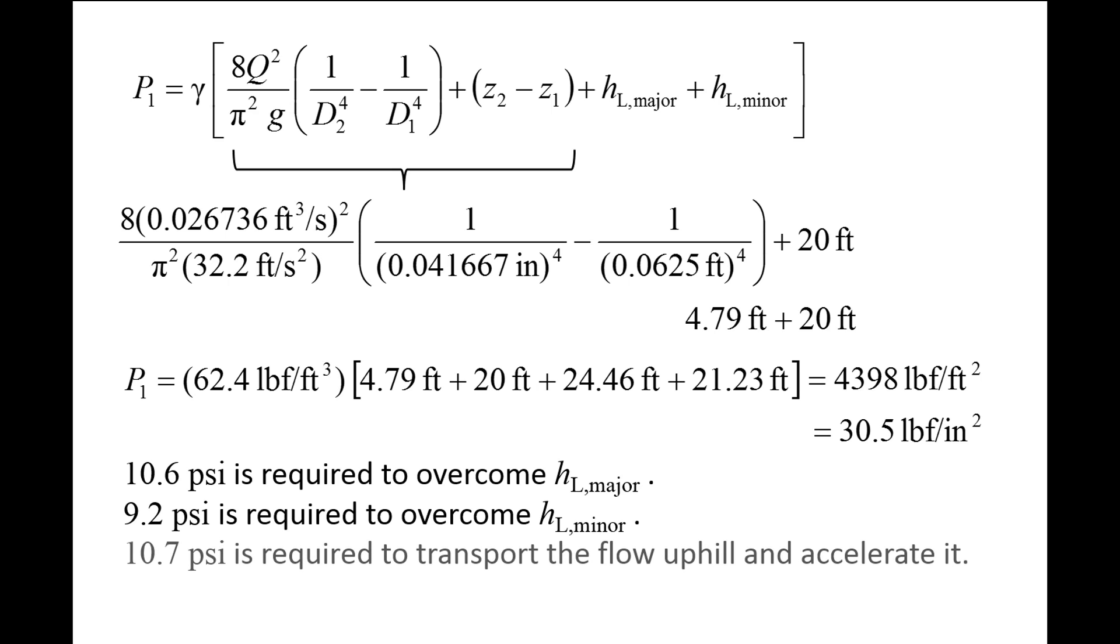If we multiply the two remaining terms, 4.79 feet plus 20 feet, with the specific weight, we obtain 10.7 psi. This means that only 10.7 psi would be required to transport water uphill and accelerate the flow if there were no frictional losses. In other words, about two-thirds of the required pressure at the inlet is used to overcome friction.